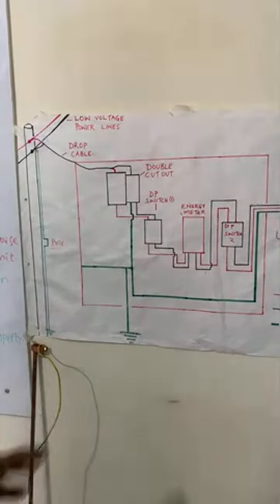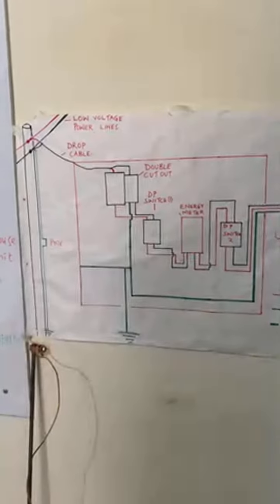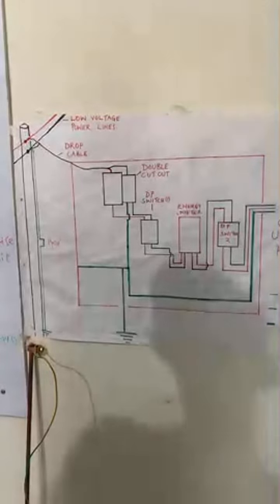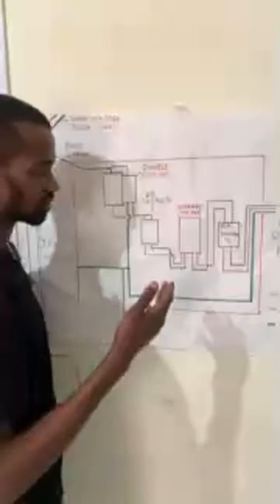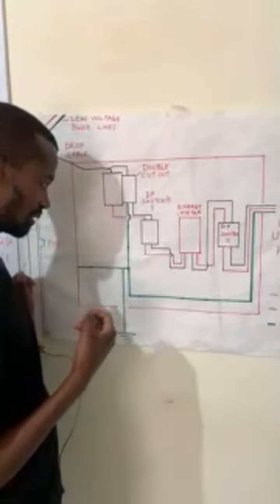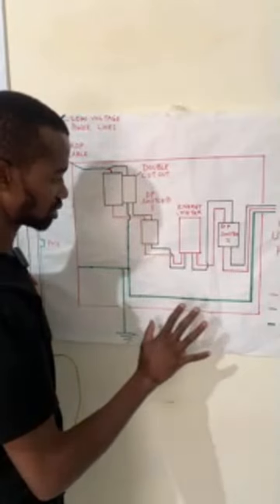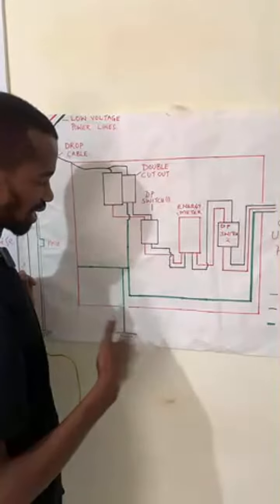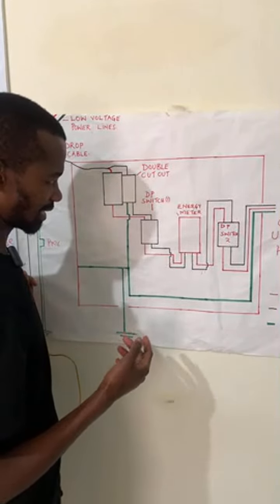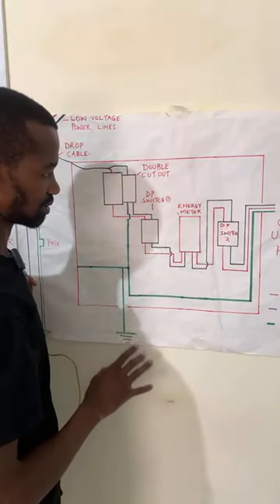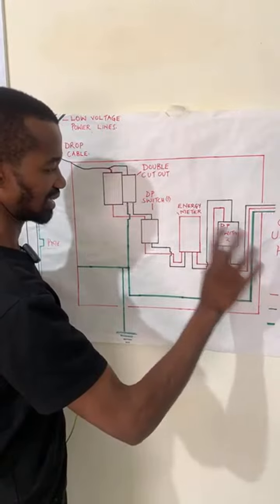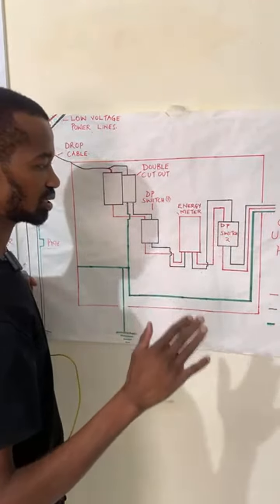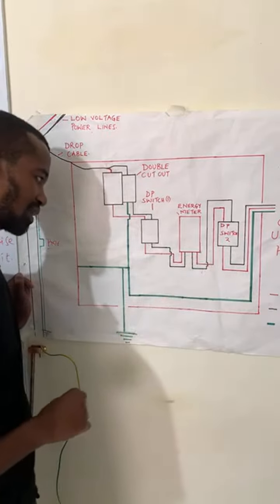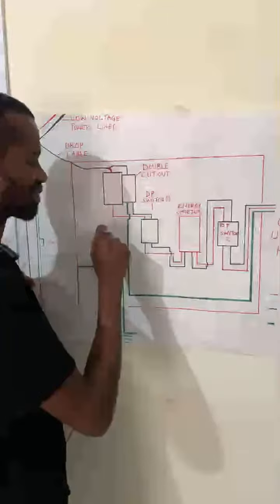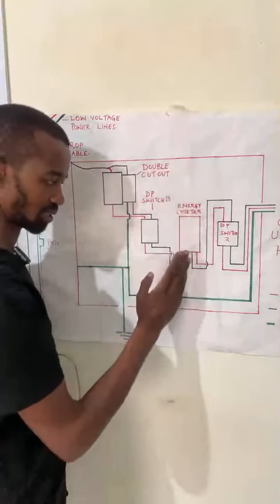Now, for this energy meter, which we were using before the introduction of the smart meters or the token meters, this connection has been used widely from the word go, and it works very well without an issue. But again, if you have this meter here, when it gets to the consumer unit, the earth remains on its own. You do not bond the neutral and the earth. So the only place that you bond the neutral and the earth is before the energy meter.